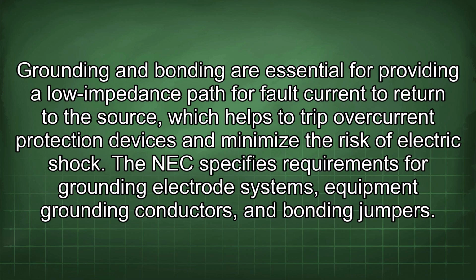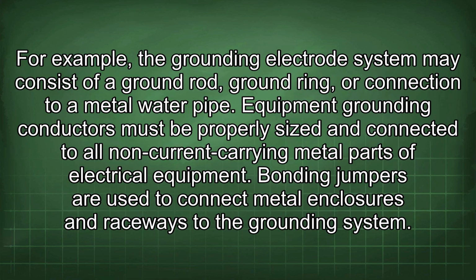Grounding and bonding are essential for providing a low impedance path for fault current to return to the source, which helps to trip overcurrent protection devices and minimize the risk of electric shock. The NEC specifies requirements for grounding electrode systems, equipment grounding conductors, and bonding jumpers. For example, the grounding electrode system may consist of a ground rod, ground ring, or connection to a metal water pipe. Equipment grounding conductors must be properly sized and connected to all non-current carrying metal parts of electrical equipment. Bonding jumpers are used to connect metal enclosures and raceways to the grounding system.